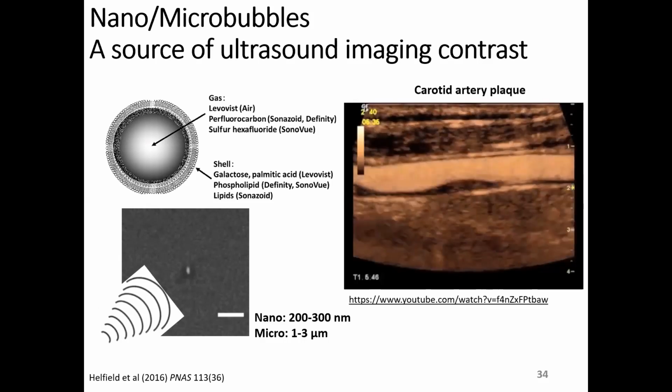So in our specific example, because it's a therapeutic application, it is an external single element transducer operating at 570 kilopascal and 500 kilohertz, which is a frequency that has been determined for the sizes of these bubbles, both the nano and the micro bubble, to be the most optimal frequency that actually causes these bubbles to burst. So we are not imaging these bubbles with the Vevo LAZR system and transducer at all. It's an external system that actually bursts these bubbles before we apply the radiation, at which point we bring them into the Vevo LAZR system to image the impact of this treatment.